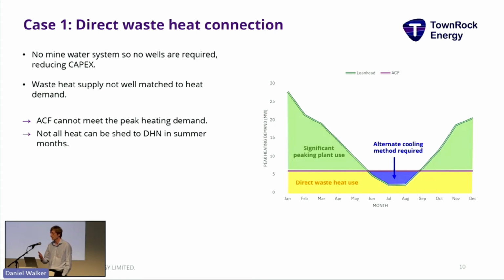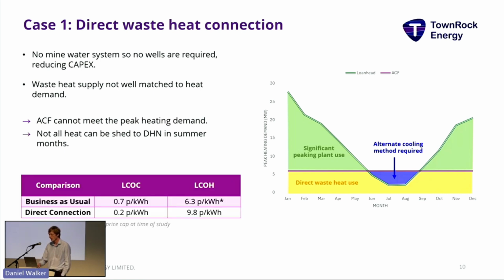On the flip side, in the summer months when there's not a demand from the network, you need alternative cooling methods for the data center — either free cooling using the ambient atmosphere, or if the temperature is too hot, you revert to mechanical chillers or air conditioning units.